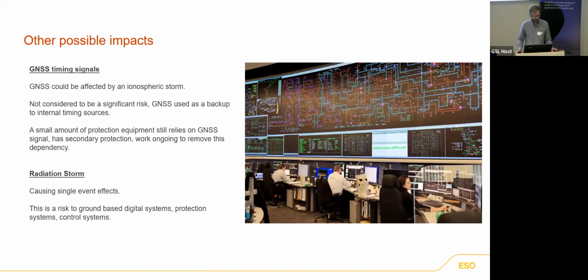Other possible impacts mentioned at the start: satellite navigation timing signals, the satellites themselves could be affected by an ionospheric storm. For us at the ESO, we do not consider that a significant risk because we have backup. We use it, but only as a backup to internal timing sources. We do have a small amount of protection equipment that still relies on this signal, but I think actually all assets have secondary or redundancy, so that they have backup protection that is not reliant on that timing signal. And there is work ongoing to remove that dependency.